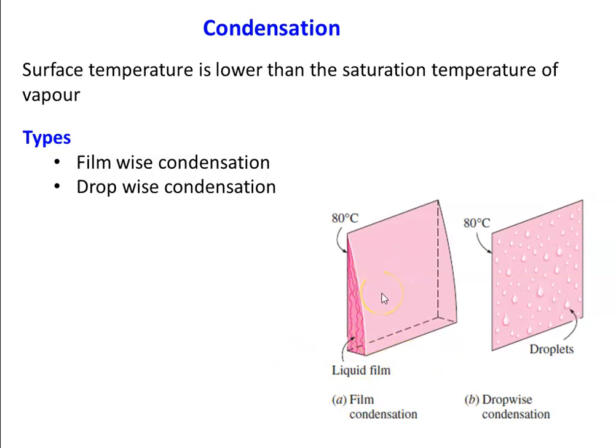In filmwise condensation, there is always a layer of liquid present. Heat is transferred between the vapor and the surface through this liquid layer, which offers some resistance, so the amount of heat transfer and condensate is less. It is very difficult to maintain dropwise condensation. All heat exchangers and condensers are designed only for the filmwise condensation method.